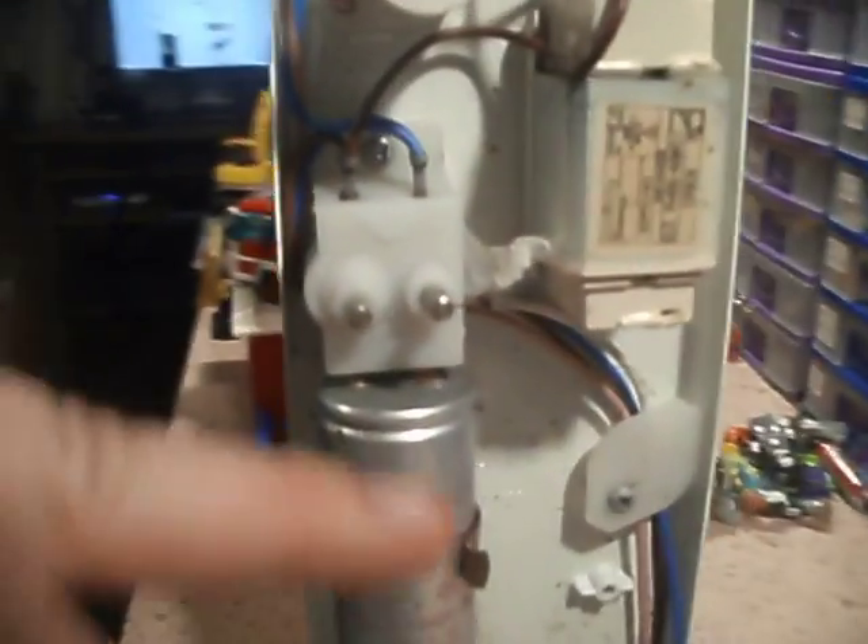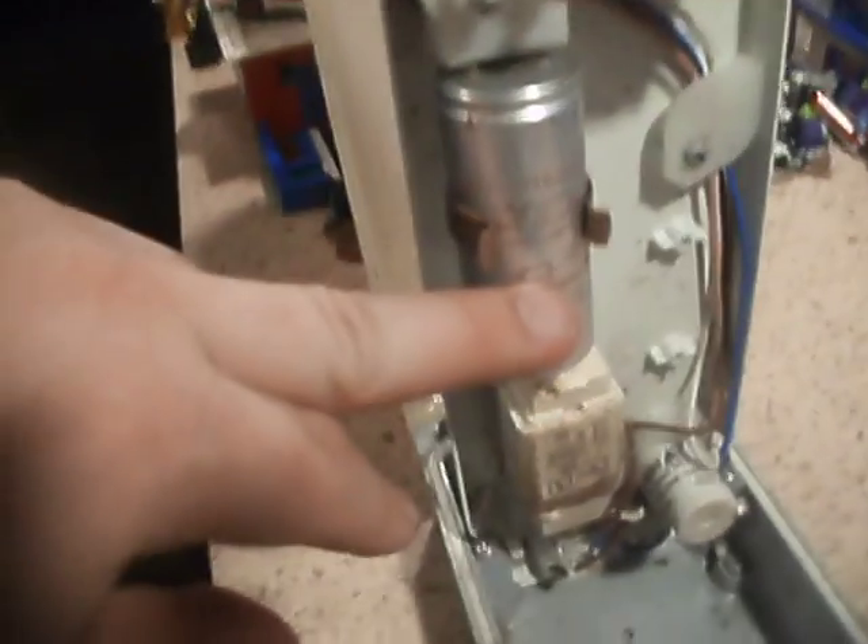And so you can loop up to another light fitting. You can put live in, neutral, live out, neutral, or round the other way, whichever way it is on the circuit — that won't matter with this. It's actually a good idea, because when you're working on this, that then isolates this whole unit from the power. Of course you have to watch that the ballasts aren't charged.